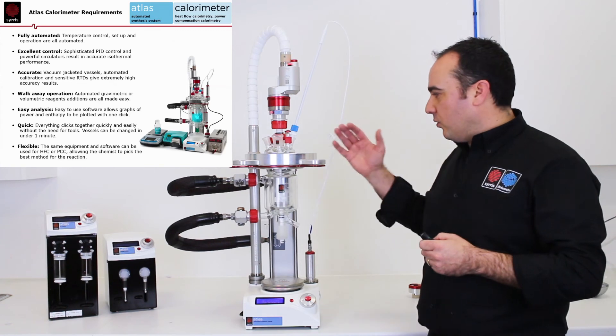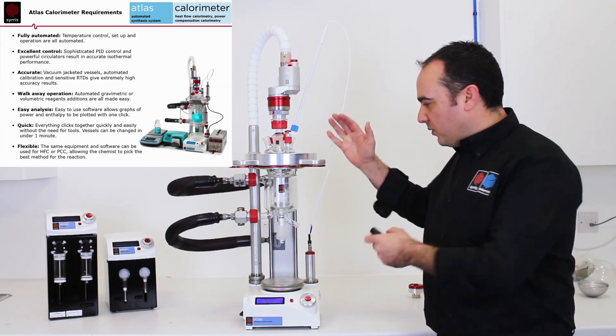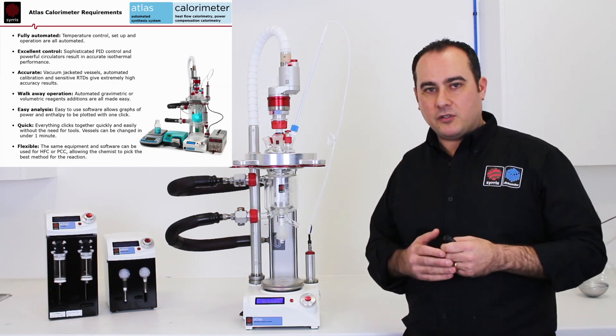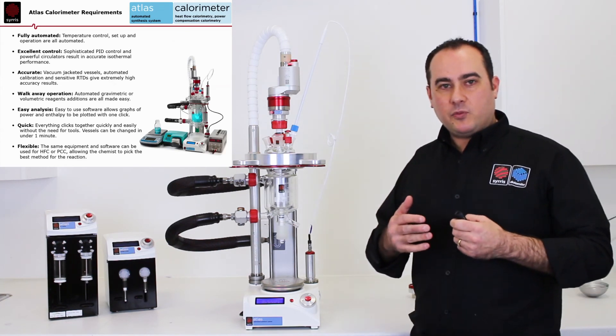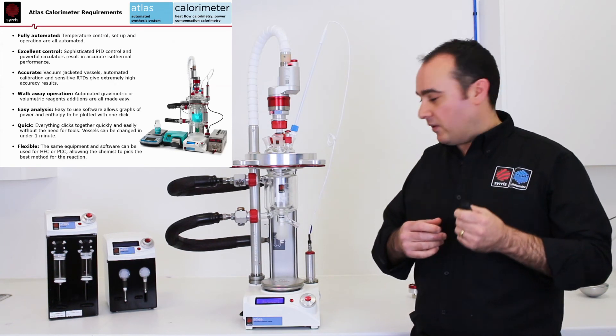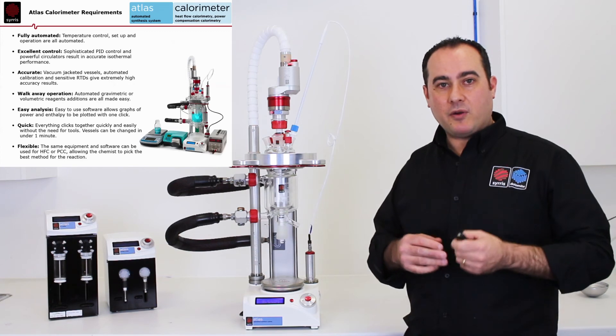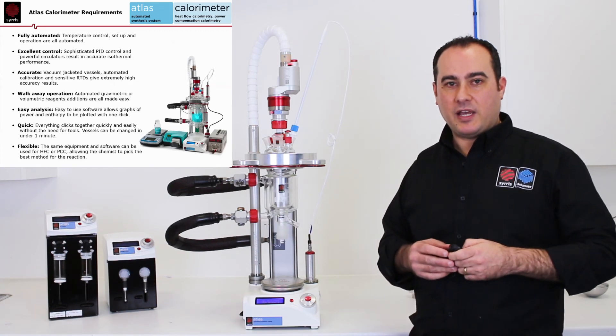The system can also be tailor-made specifically for calorimetry. With this configuration, we can measure the heat of the reaction. It's very powerful, highly specified reaction calorimetry which can do power compensation calorimetry and heat flow calorimetry.